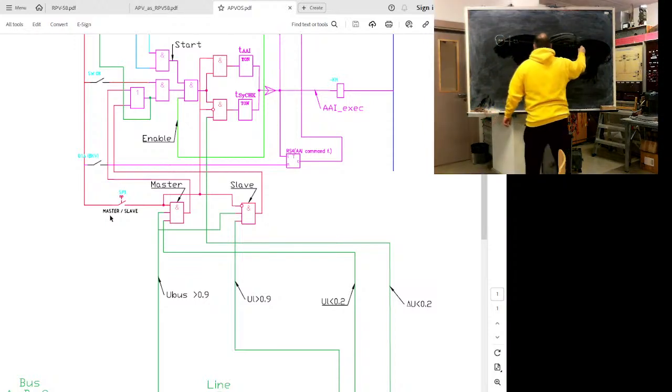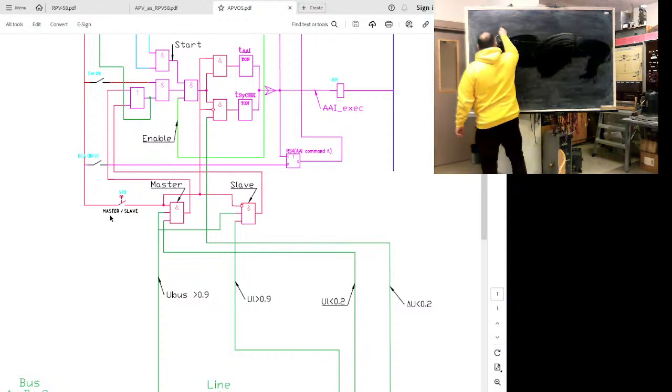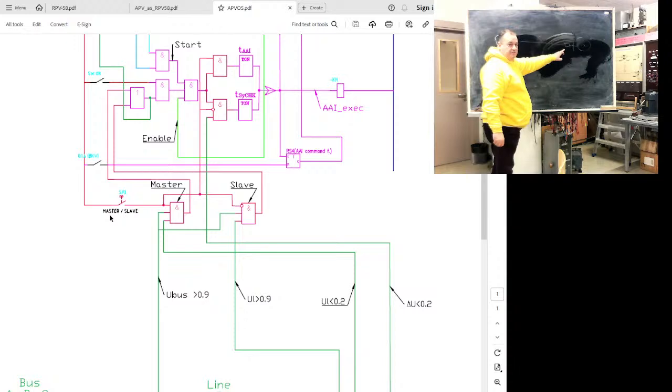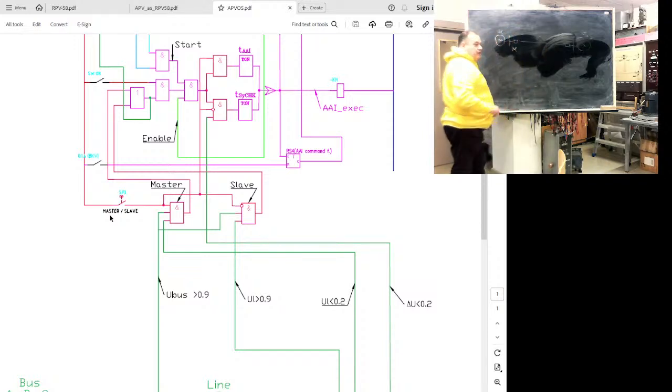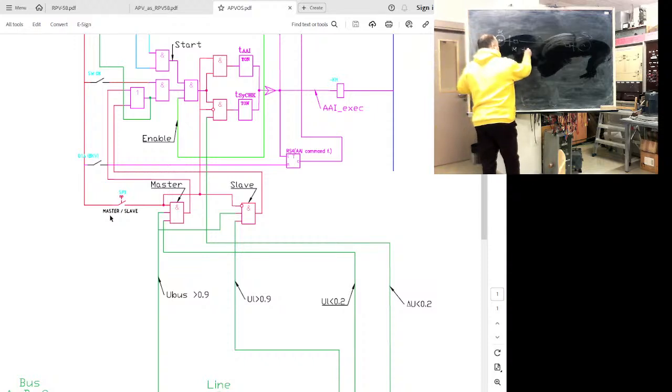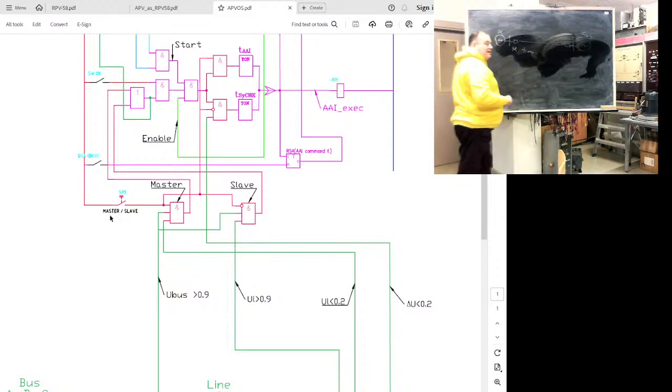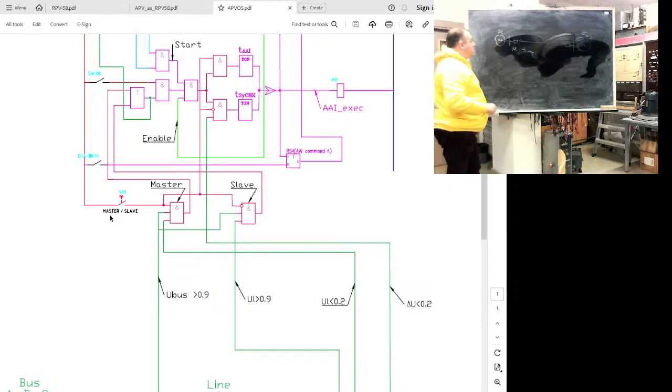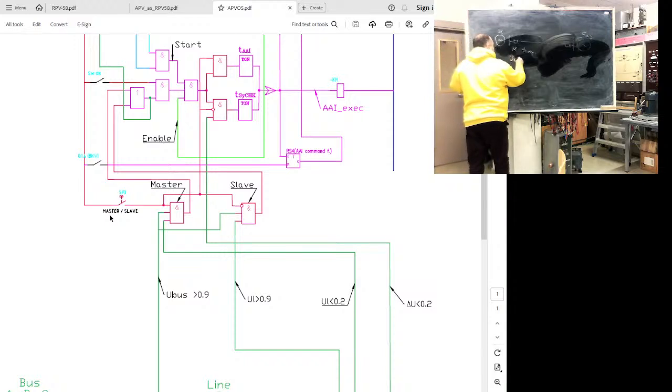We are here, system to system 1 was false, both switches are disconnected. Someone needs to start. We need to perform reclosing of this line. The master side should go first. The master waits for the reclosing, and then, when it's possible, switches on. The conditions are: all buses have voltage greater than 0.9 per unit, and the line is less than 0.2 per unit.